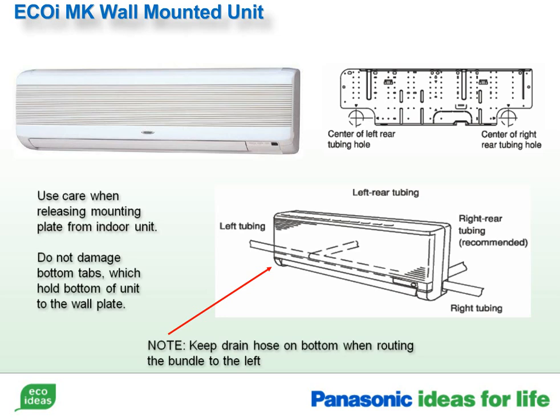The wall-mounted model can have the refrigerant and condensation lines exit from the left, right, or back. The minimum height from the floor is 5 feet. Be careful to run the condensation line as low as possible so that the pan will drain properly. Do not use P-traps on the drain, but if they are required, install them as low as possible so that enough head will build to push the condensation through the trap.